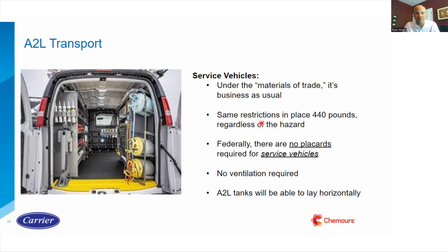The reason you don't have to do it on your service van is because Chemours and other refrigerant manufacturers went to the U.S. Department of Transportation to get a clarification that you guys are considered materials of the trade. And we're putting that in quotes because I don't know exactly what that means. But basically, what it means for my purposes is that you are not delivering refrigerant to a job site. What you are doing is using the stuff on your van to install things at a project. It's a temporary situation. And for some reason, that gets labeled as materials of the trade. And you could have up to 440 pounds that way.